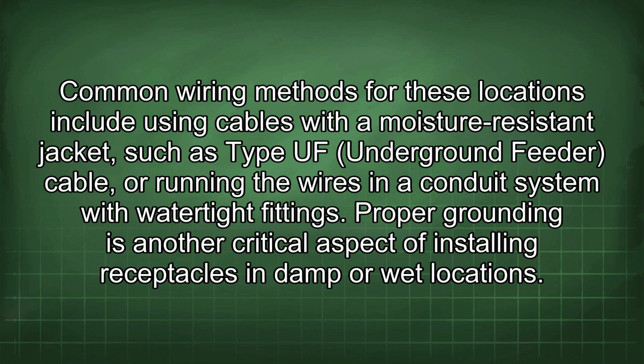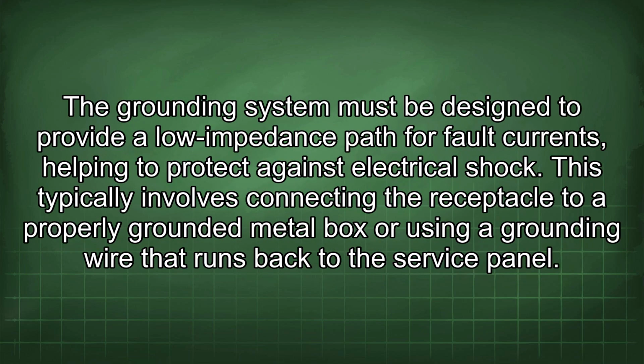Proper grounding is another critical aspect of installing receptacles in damp or wet locations. The grounding system must be designed to provide a low impedance path for fault currents, helping to protect against electrical shock. This typically involves connecting the receptacle to a properly grounded metal box or using a grounding wire that runs back to the service panel.